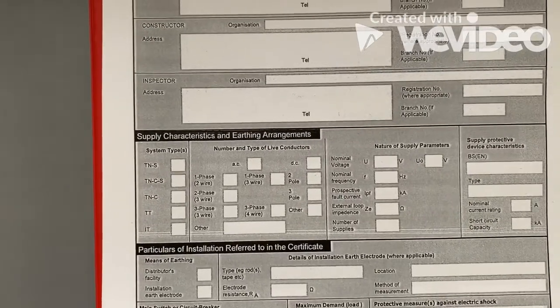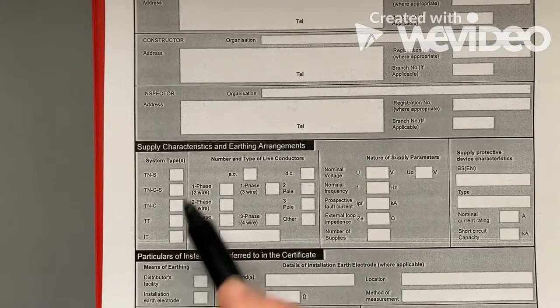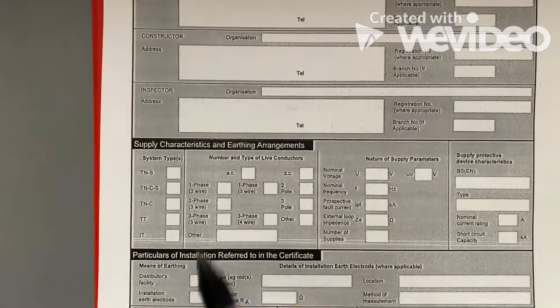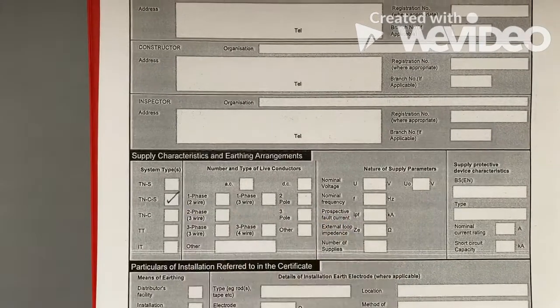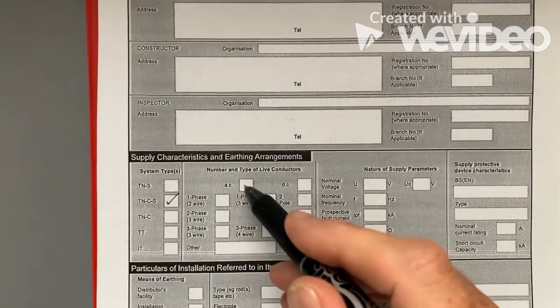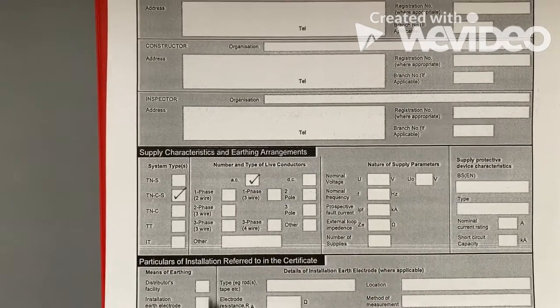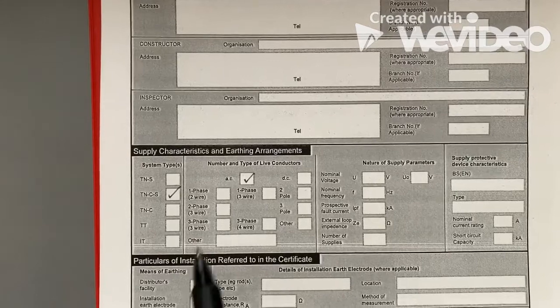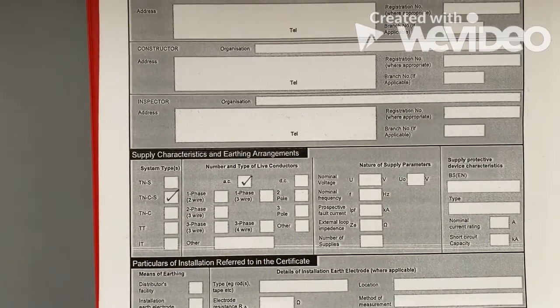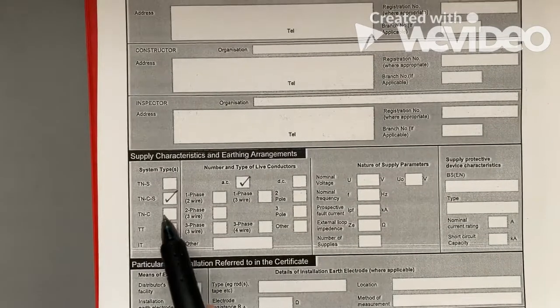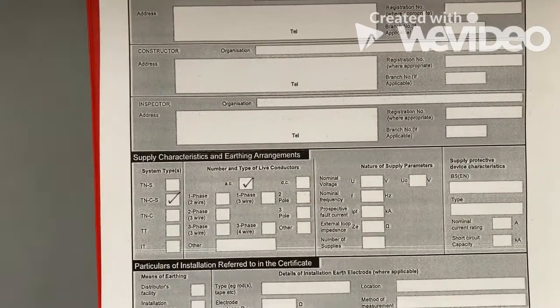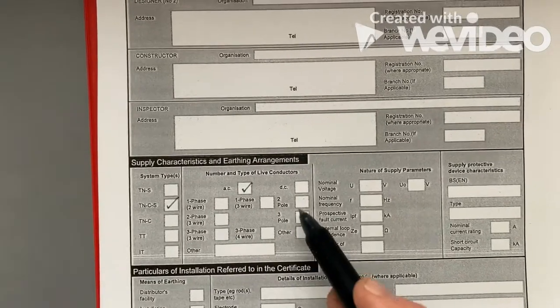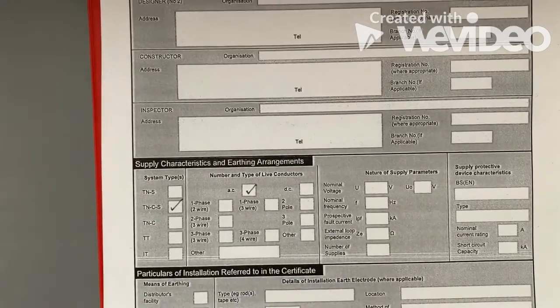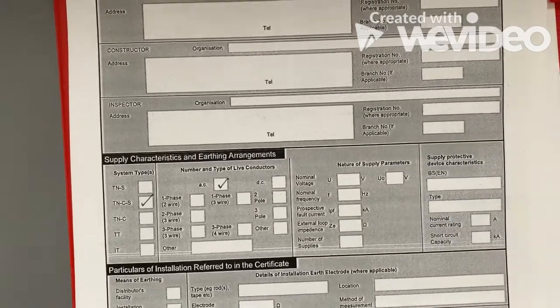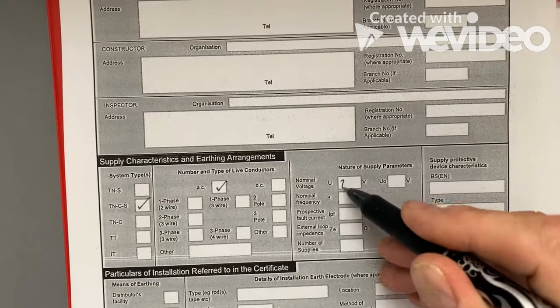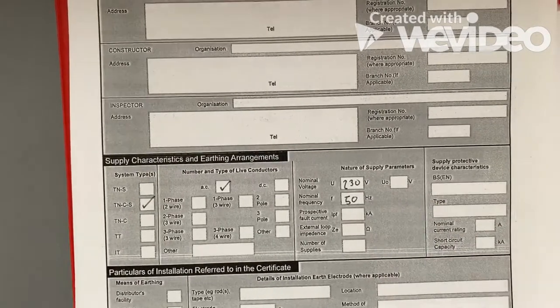You could normally get these from your network, but what you'd see is it would either be a TNS, TNCS. So for this example, we'll put TNCS. And the number of live conductors. So we're dealing with AC, and what we're saying is it's one phase, single phase. Now TNCS, so it's a combined and then separated. So we've got one wire, one phase, two wire coming in, two pole DC, three phase. So we would go through those boxes and then we would get given the nominal voltage. So we could say it was 230 and we could say 50 Hertz.